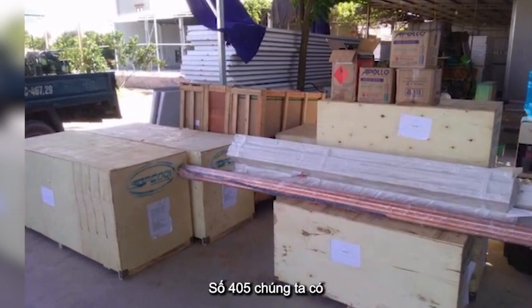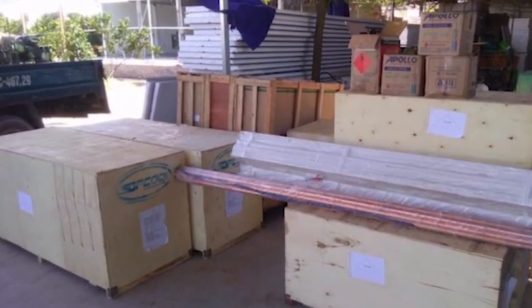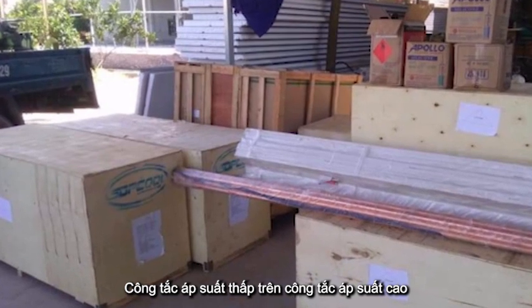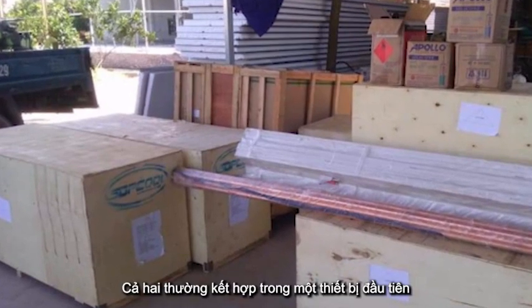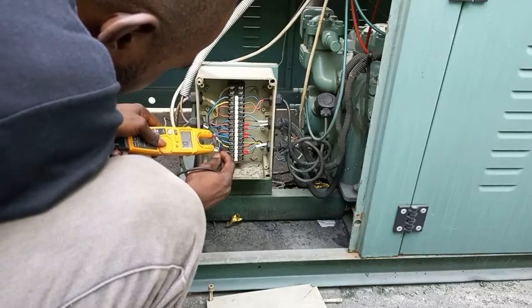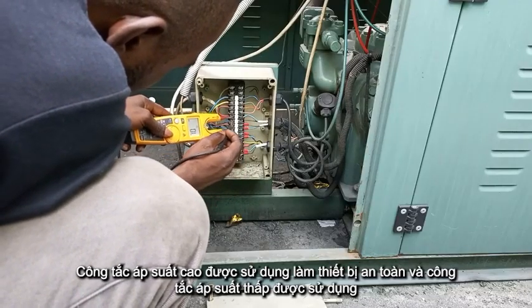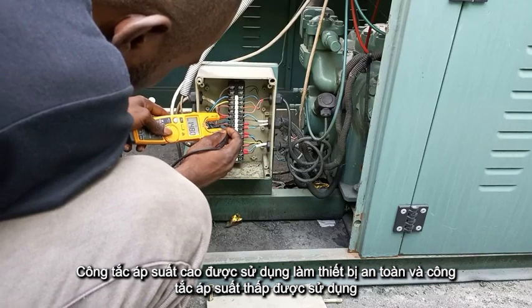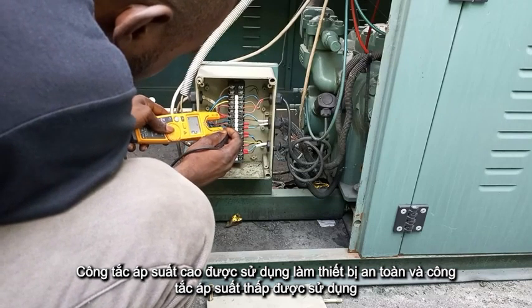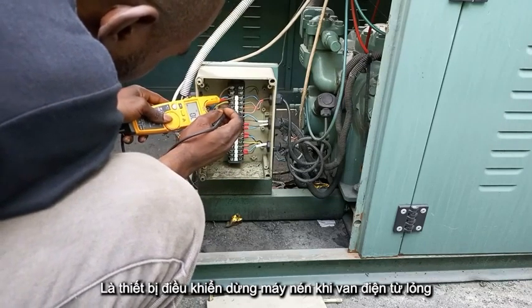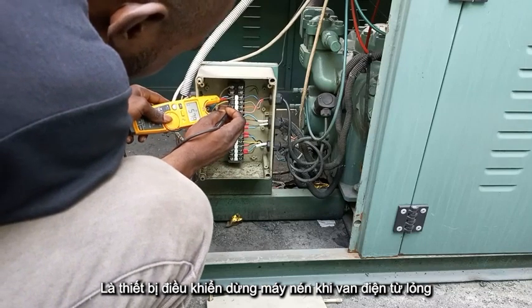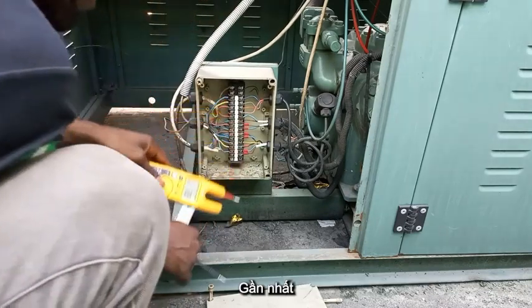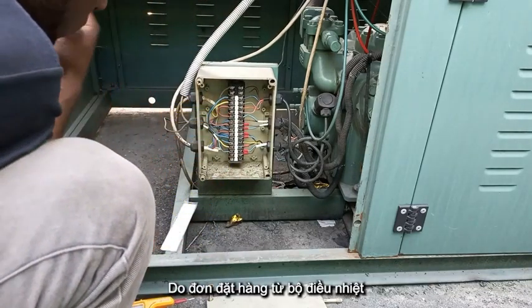In number 4 and 5 we have the low pressure switch and the high pressure switch. They both are normally combined in an only device. The high pressure switch is used as a safety device, and the low pressure switch is used as a control device to stop the compressor when the liquid solenoid valve closes due to an order from the thermostat.